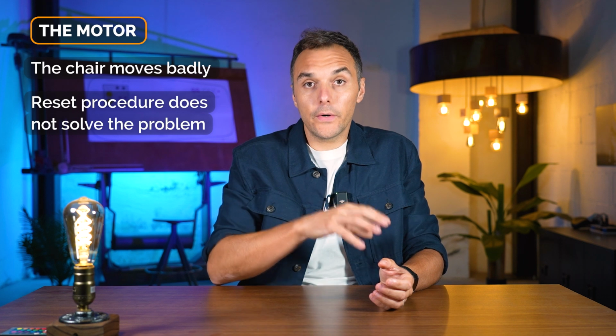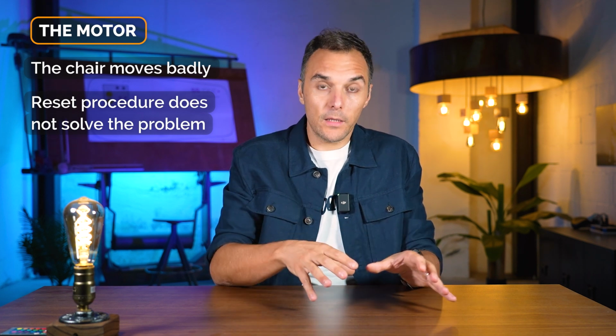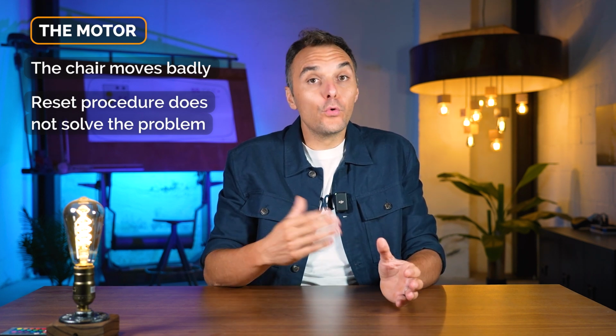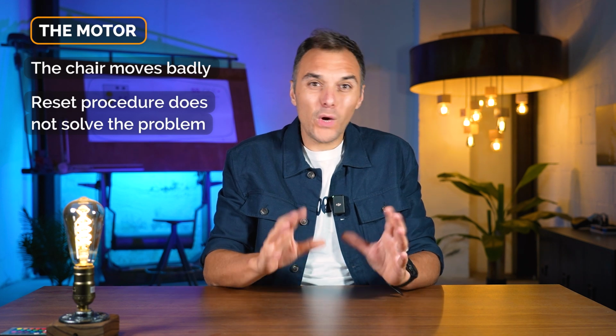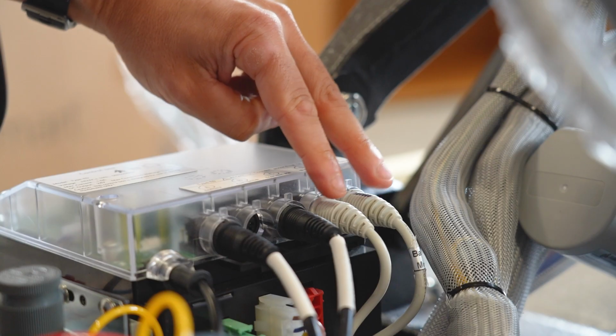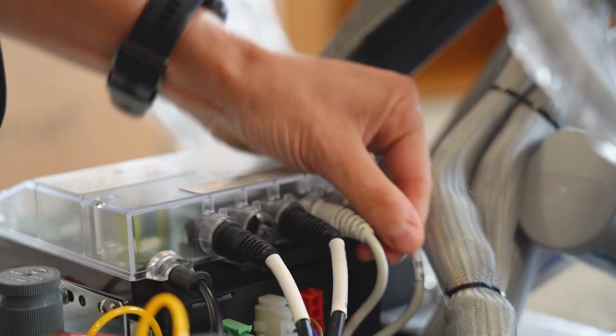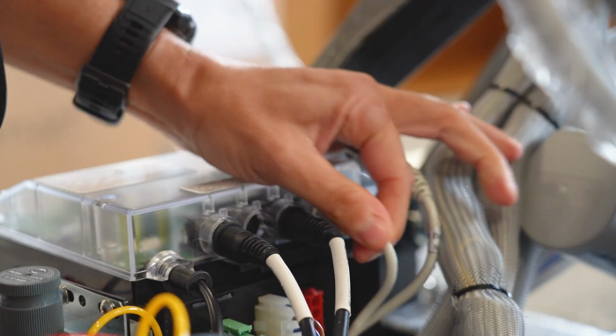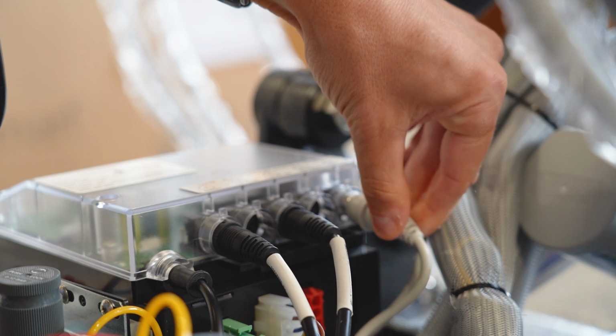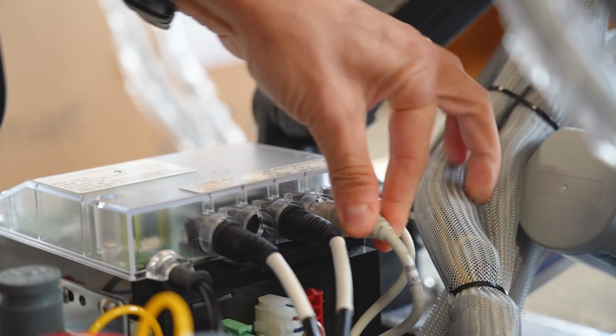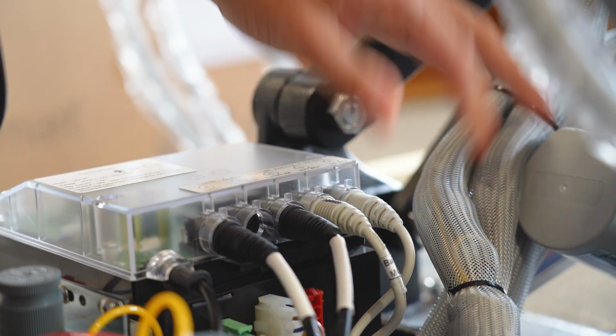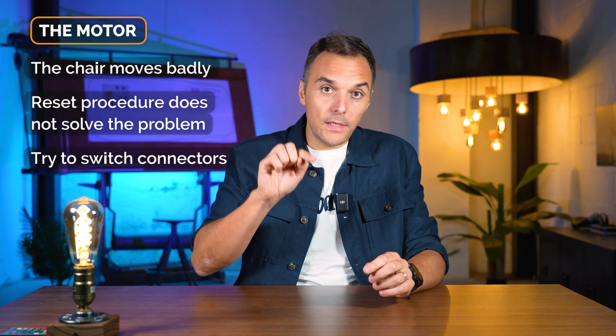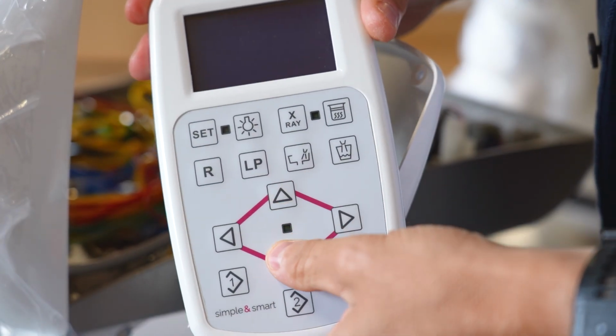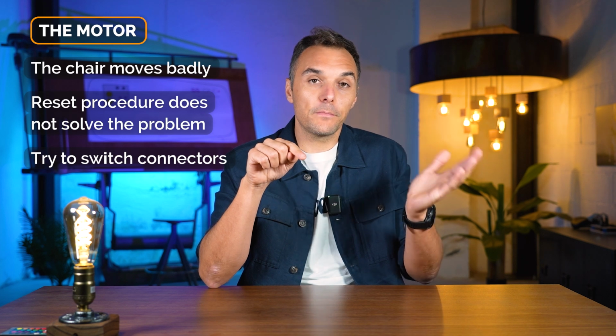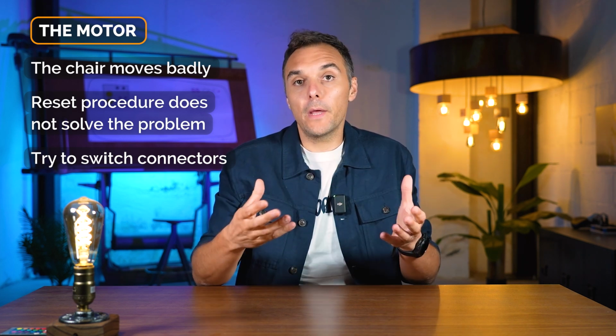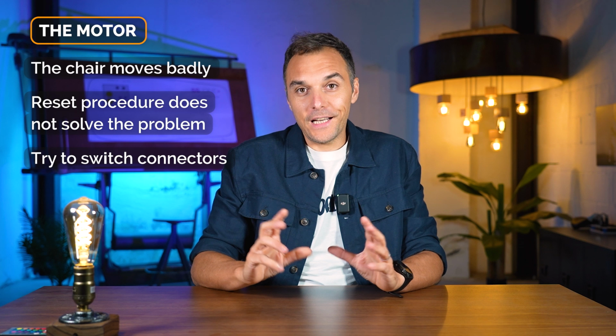So if doing the reset doesn't solve the situation, we can check the motors. To check the motor before removing it from the dental chair, which is a fairly complex task, you can switch at the chair base - there are two connectors, one for the seat motor and one for the backrest motor. If you switch these two cables and insert them in the opposite way, inverting them, we can check by pressing the doctor's control panel whether the chair backrest is moving back and forward, or if the problem remains as before. So I'll try to make this a bit clearer.